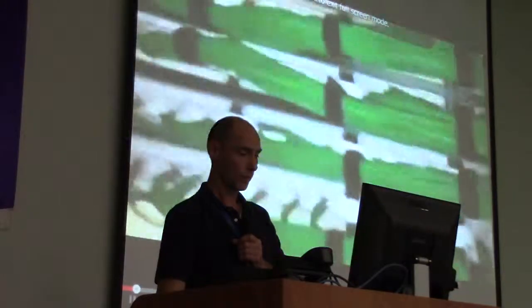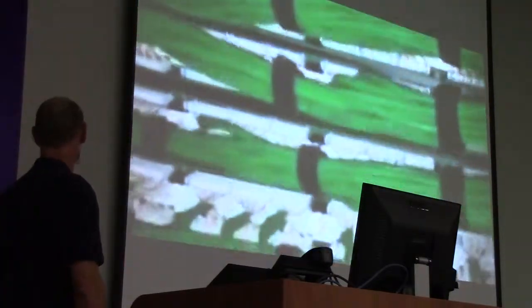And now I've got a demonstration of a guy who really did a good job in a wiring closet. We have our vertical cabling in the back of the patch panels. As you can see, all the cables are nice and neat, punched down, with no excess weight pulling on the cables, causing them to become loose or eventually wear out from the weight pulling down on them from the patch panel. As you can see, we move up to the next step. We have the same thing, and on and on. This particular wiring closet has 9 switches.